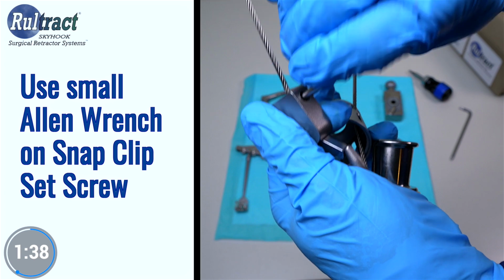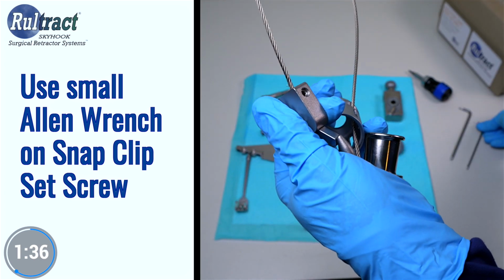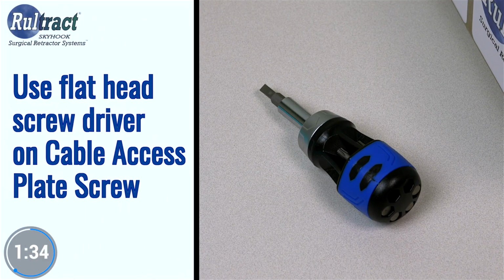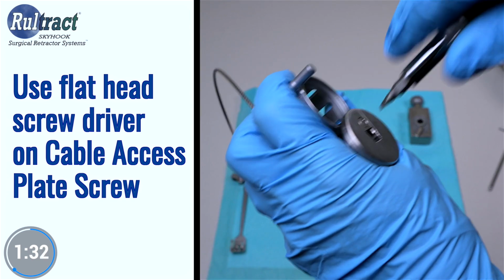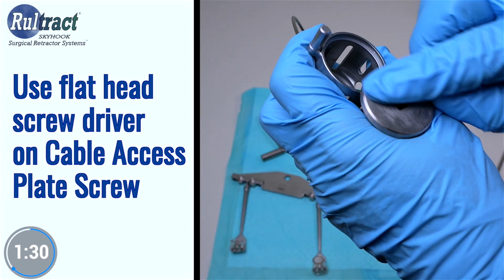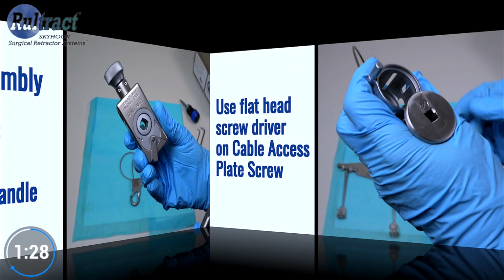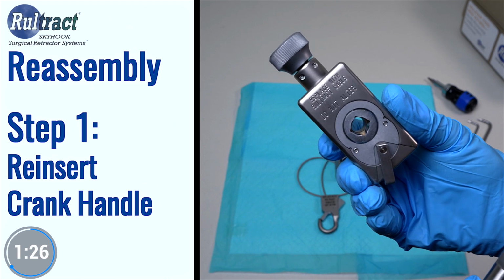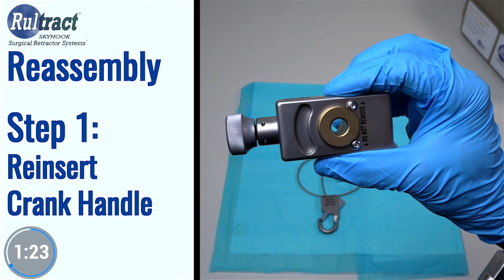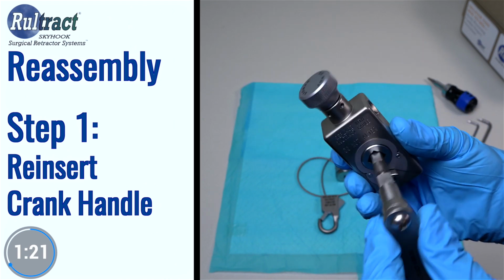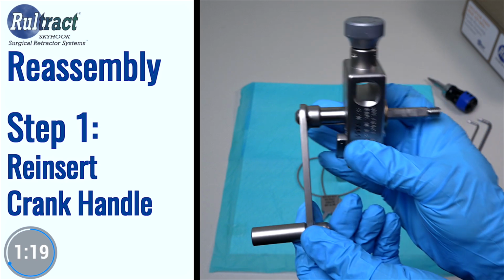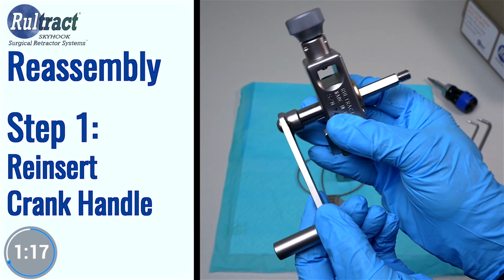This doesn't need to be over-tightened. Just make sure that it's tight and very secure. Use a flathead screwdriver and check your cable access plate screw. Run your finger over to make sure that it sits flush. Insert the crank handle into the gearbox. Be sure to insert it into the square hole right above the ratchet reversing lever, making sure that it sits flush. There is also a square hole at the top, but that's not the correct hole to put this in.